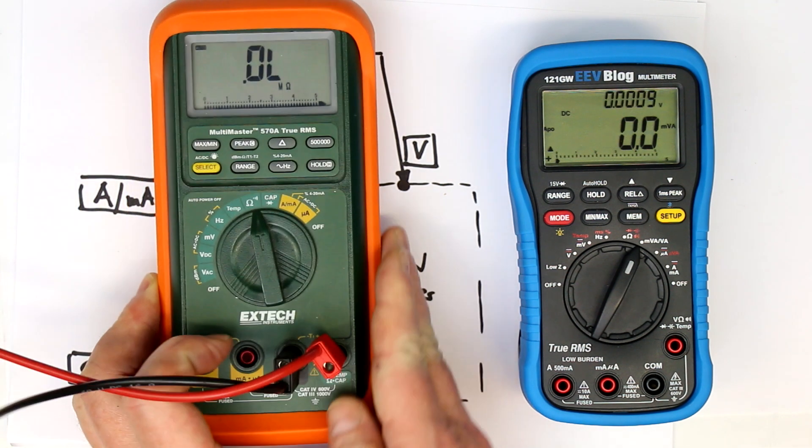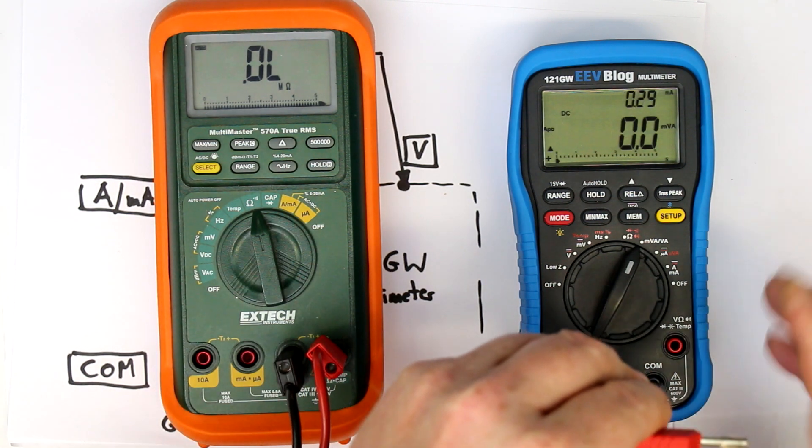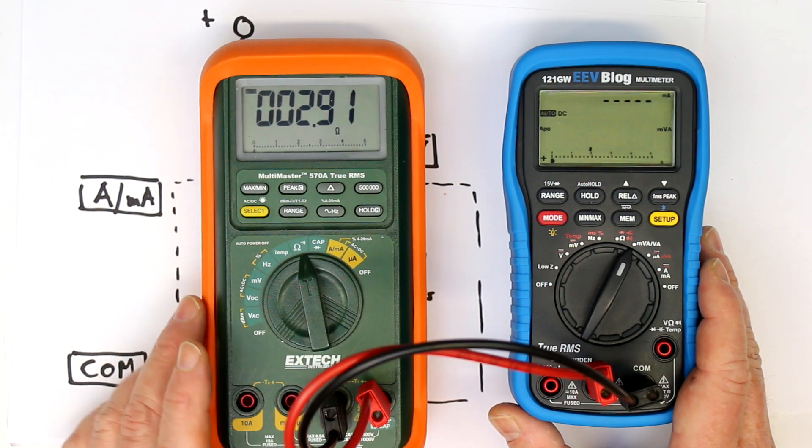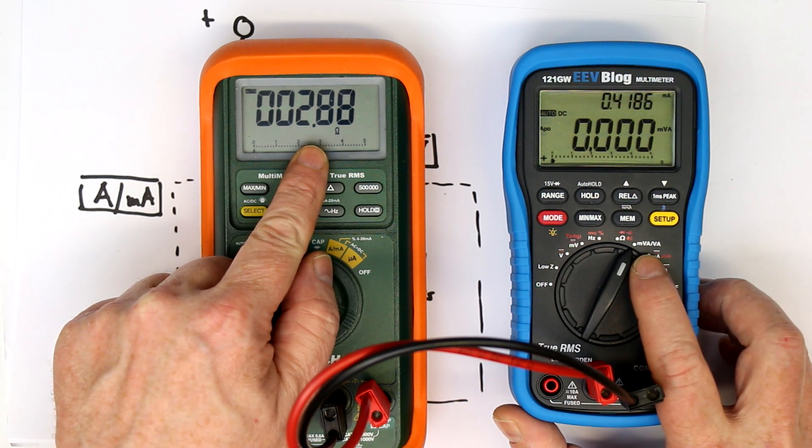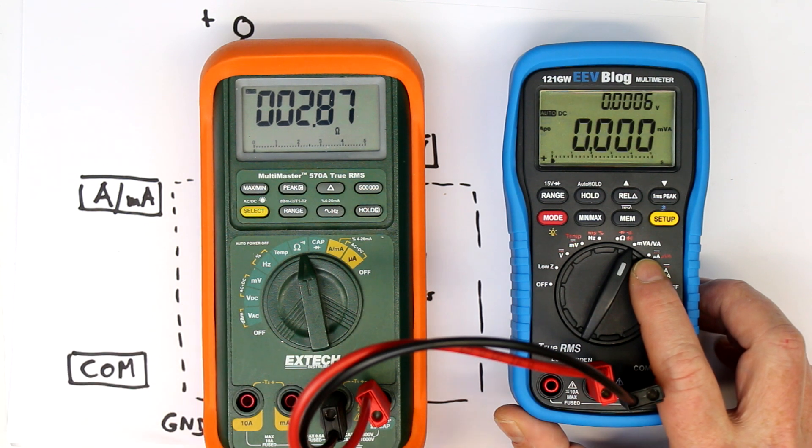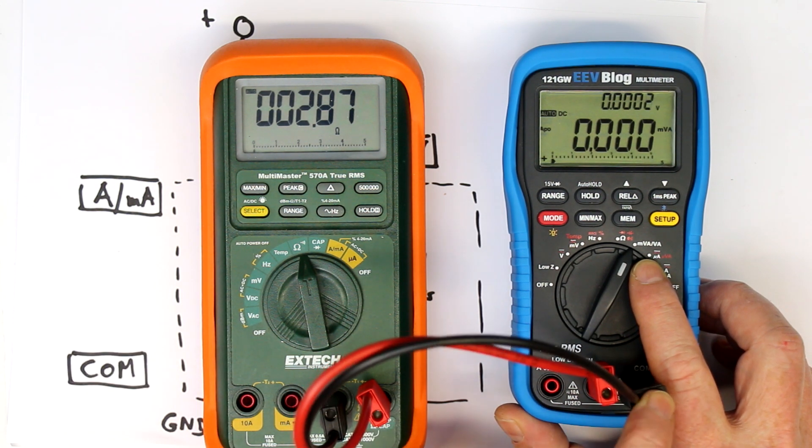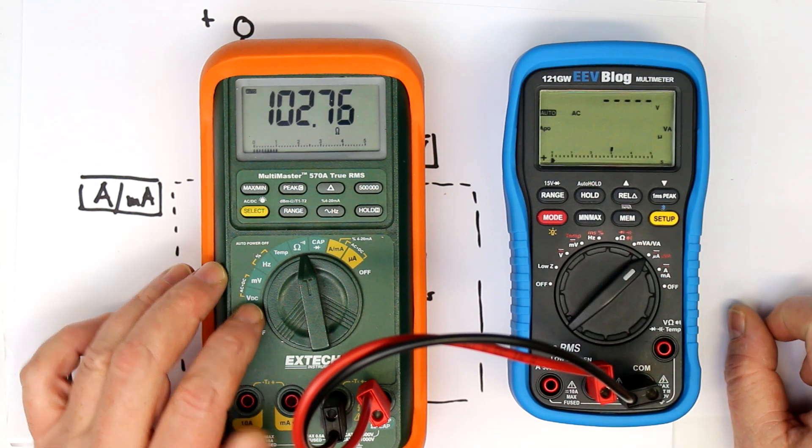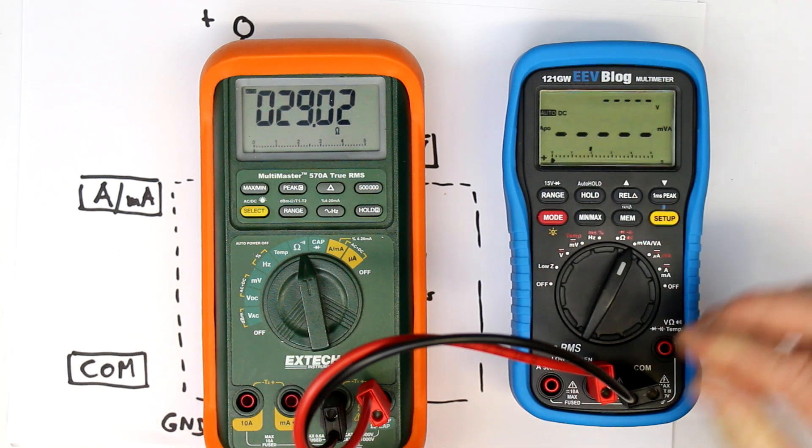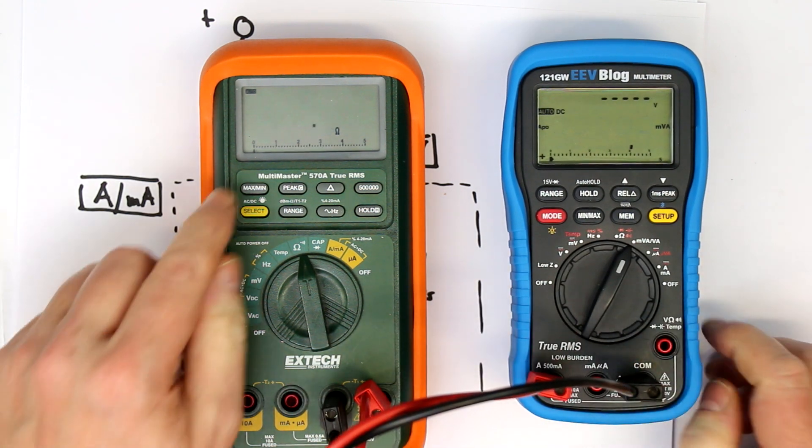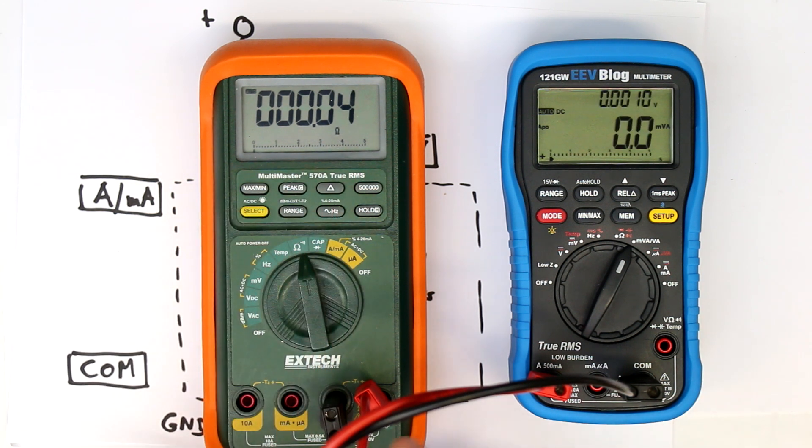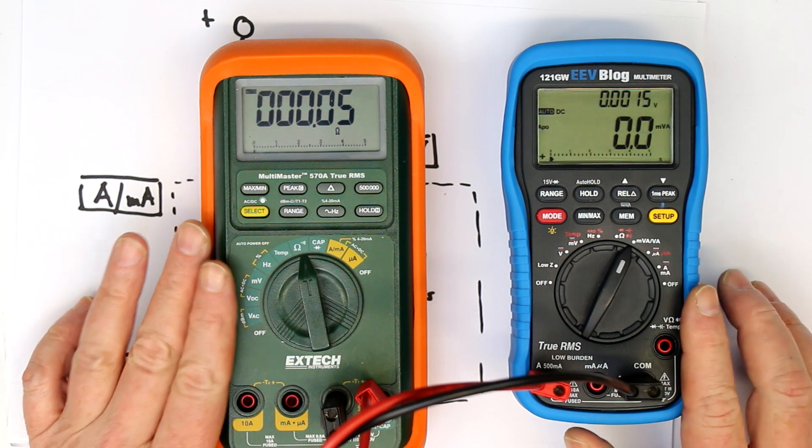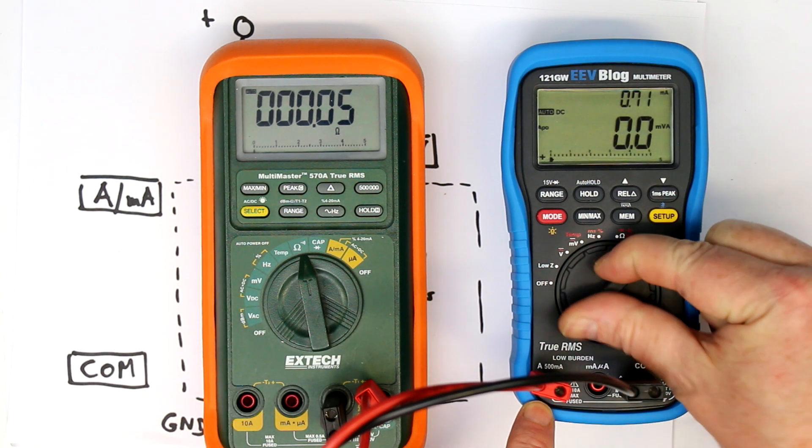Let's start with measuring the shunt resistance in the amps and milliamps terminal. You can see in the milliamps region we have 2.88 ohms all in all. I've not nulled out the resistance of the test leads and contact resistance, so let's leave this at 2.8 something. In the microamps range we have 102.8. If we go to the amps terminal, that should be a few milliohms—50 milliohms minus the lead resistance minus the contact resistance. So we have three different shunt resistors depending on the input terminal and range.